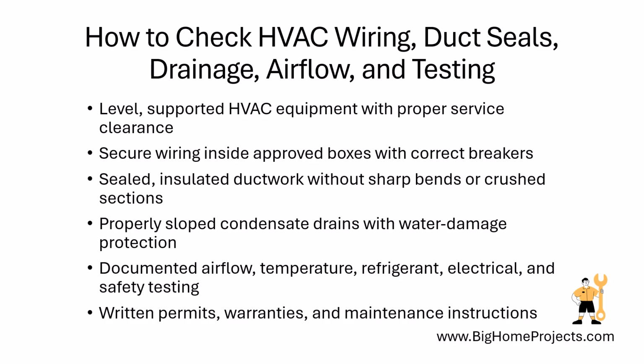Condensate drain pipes should slope properly, include a safe termination, and have protection against water damage near ceilings or walls. After installation, the contractor should test airflow, temperature difference, refrigerant levels when applicable, electrical readings, and system safety controls rather than simply turning the unit on. Ask for written measurements, permits, warranty information, and maintenance instructions, because professional work should be explainable and documented.